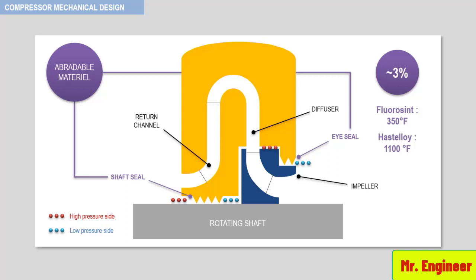Deterioration of labyrinth seals in a centrifugal compressor is one of the major causes of reduced performance. The eye seal is affected to a much greater extent than the shaft seal, since the dP across this seal is greater.